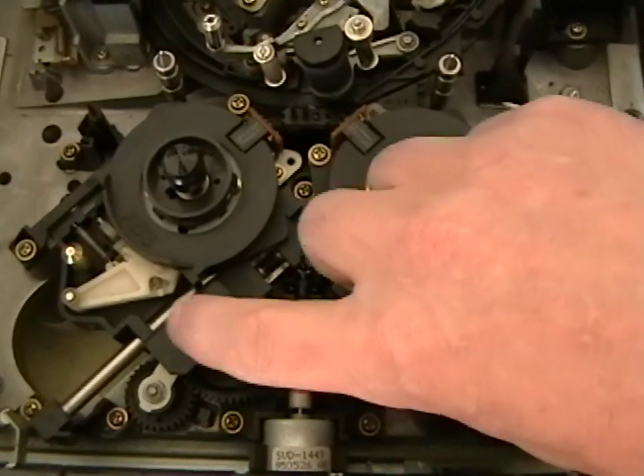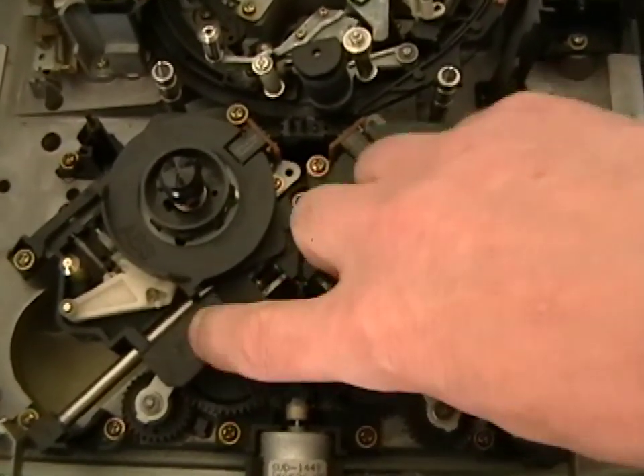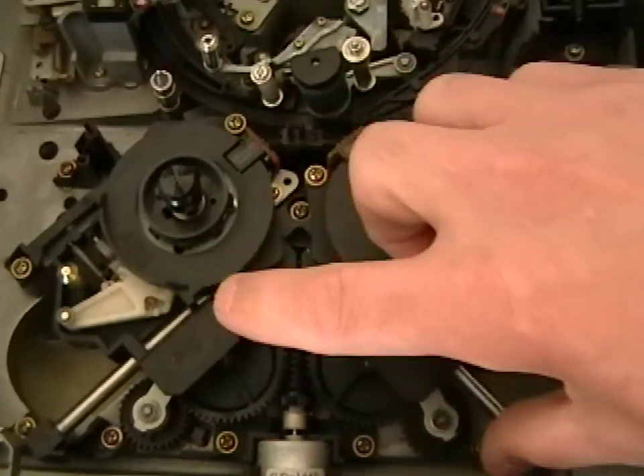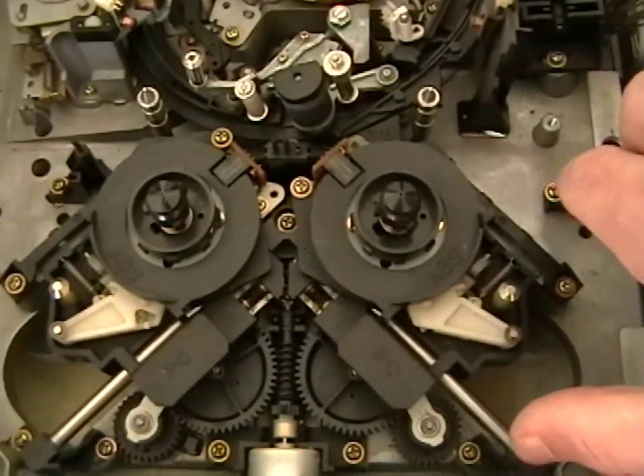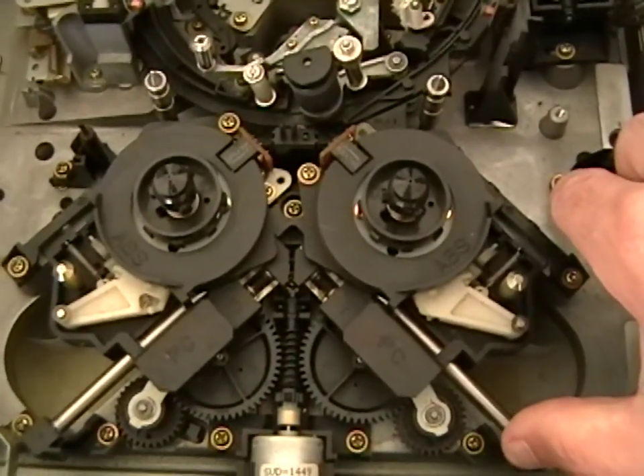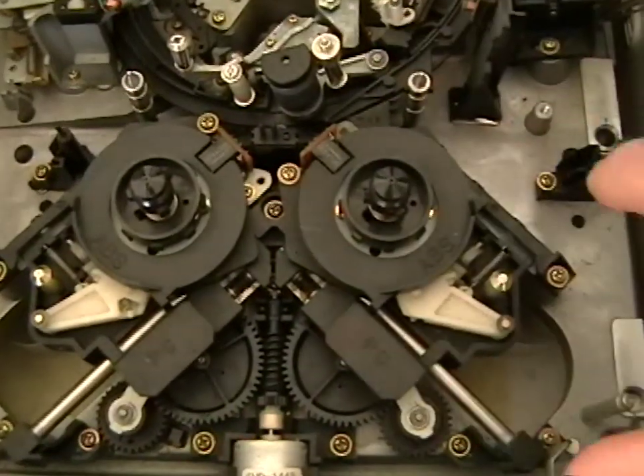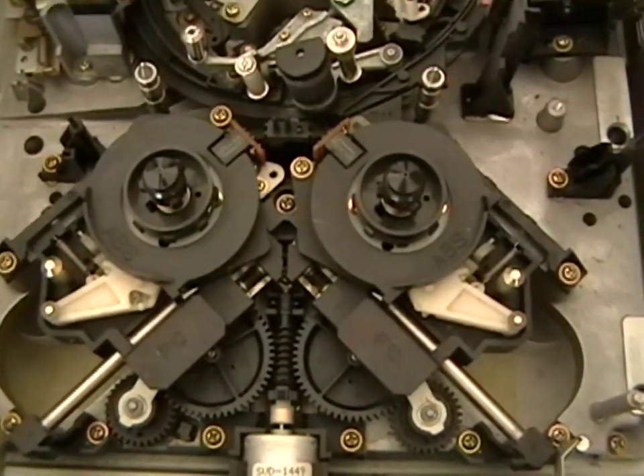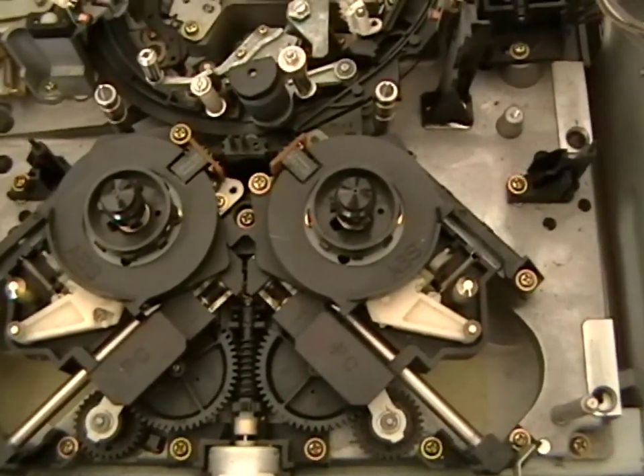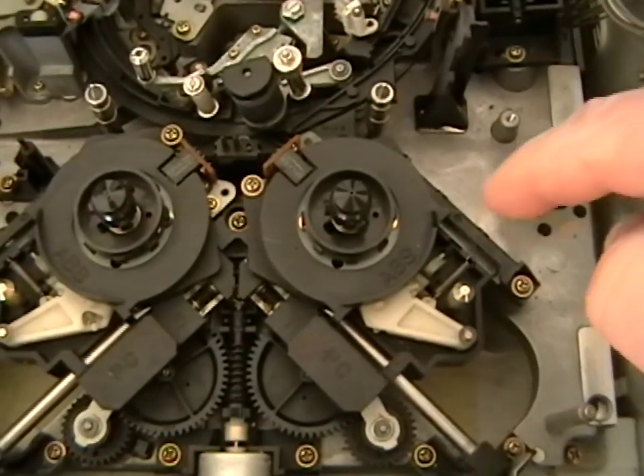If you know how to do this and you've got a schematic, you need to service this mechanism: take it apart, re-grease it, put it all back together, realign it with the gears, and it should be a very smooth transition going in and out when you load a tape. That is your number one error code problem on these UVW machines.